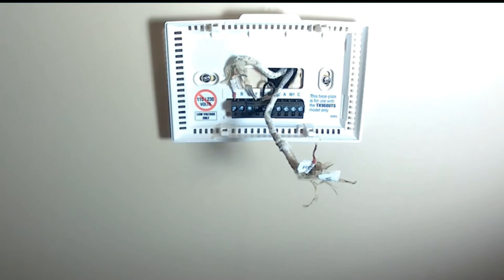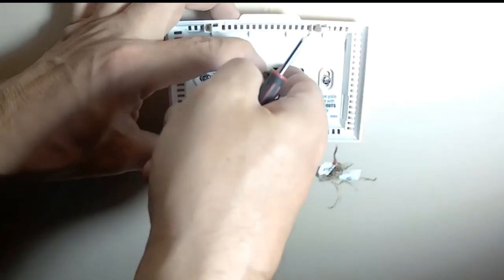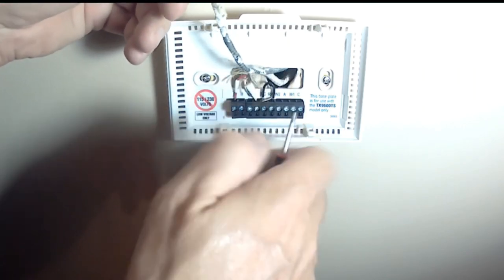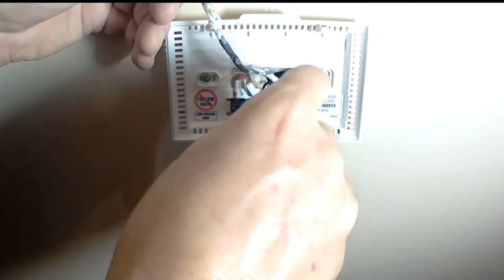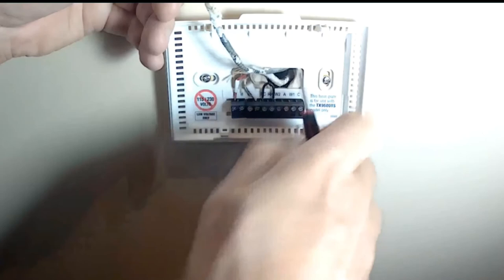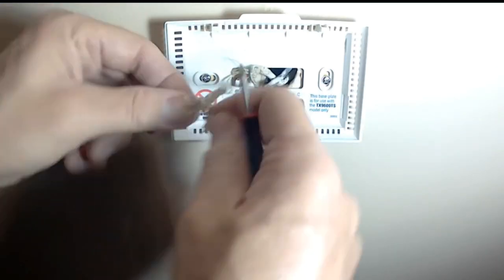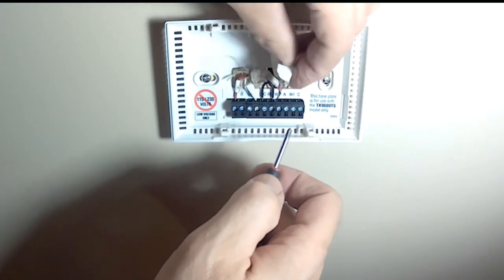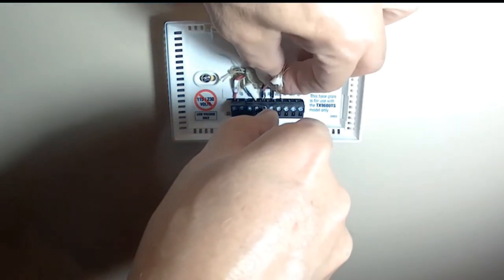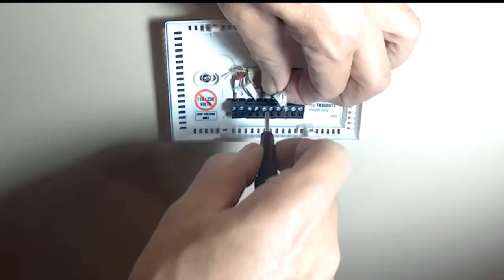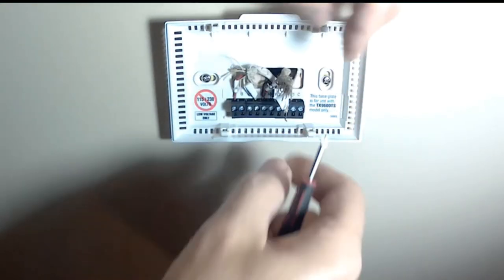Make sure these things are out of the way of the batteries because the batteries go right up here. And make sure you have no loose wires sticking out because of the electronics in the back. Now we have an RC and a W. So the RC goes right along with that black jumper. Got to back that screw off. See if I can push that jumper down a little bit more. Doesn't look like it. That's how long it is. Tighten up the RH again. And RC goes right in here. Twist it around. RC. Stick that in there with that one. A little bit more so it goes a little bit deeper. That's probably deep enough. There we go. Give it a little tug.